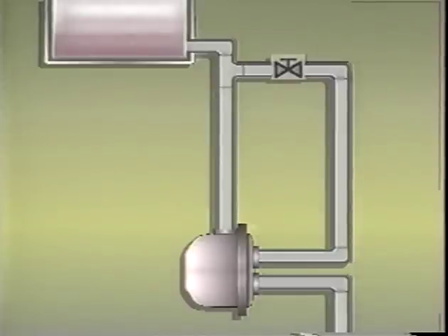To avoid differential shock arising from this situation, use an F and T trap and back vent it to the top of the vertical line to maintain near equal pressure throughout the riser, even if a slug of condensate forms.